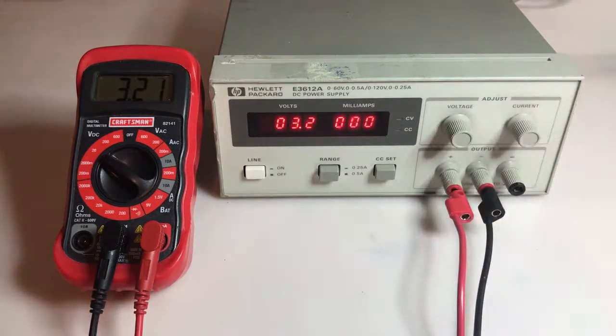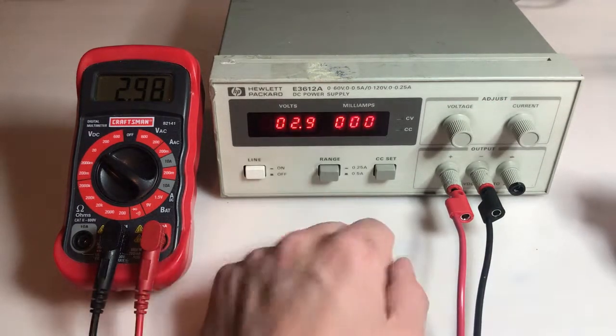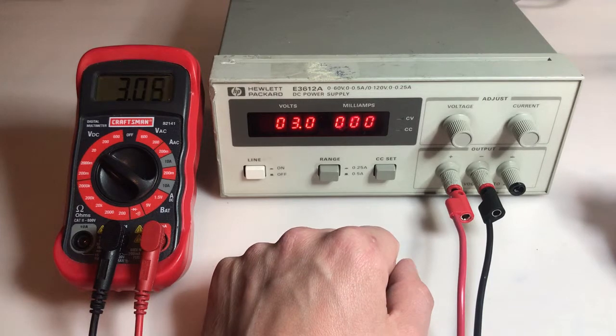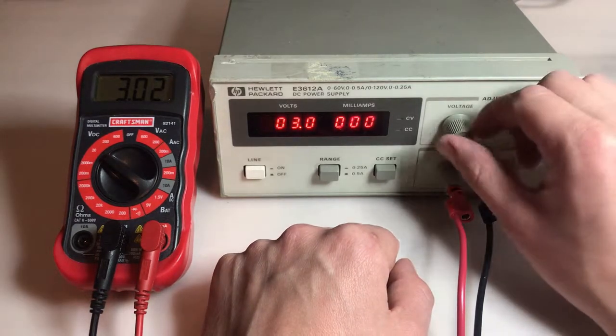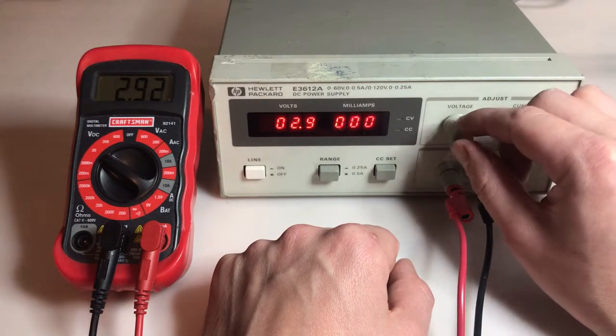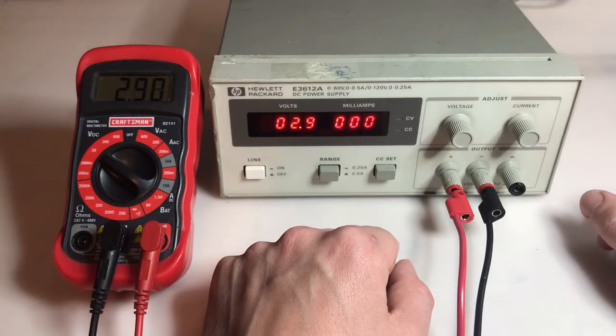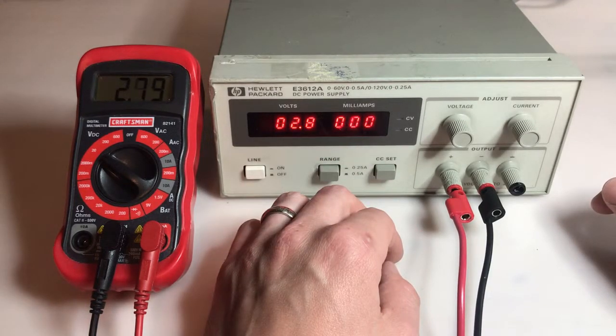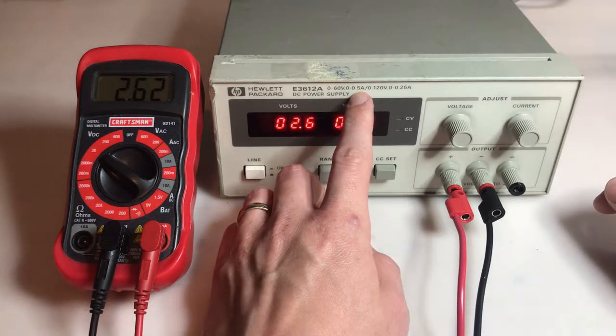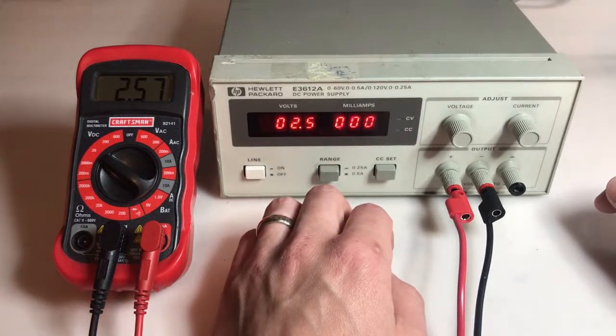So obviously it's not able to reach the set point voltage at all. The other thing this has is constant voltage mode, which just means whatever your voltage is set to, it's going to keep that voltage maintained regardless of the load, assuming it doesn't go past your 0.5 or 0.25 amp rating.